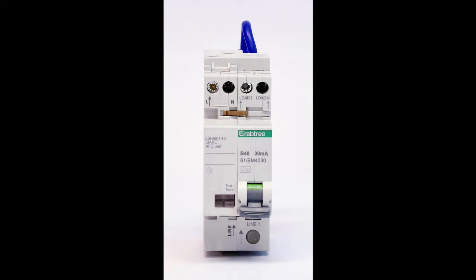It's important that installers understand that AFDDs detect the types of arc faults that cannot be detected by RCDs or MCBs. These new devices use digital technology to provide additional protection against fires caused by arcs in AC 230 volt final circuits.